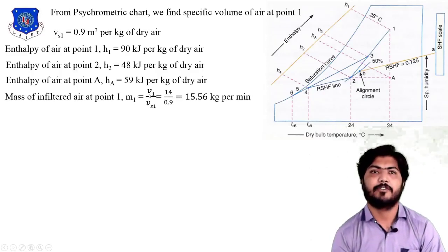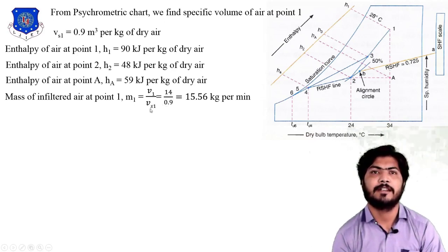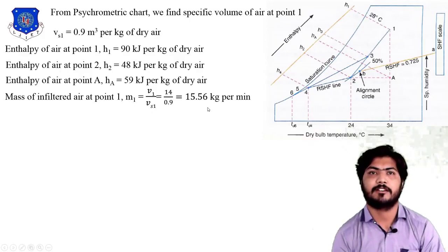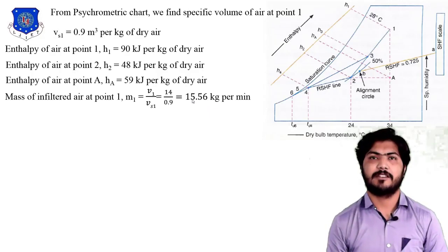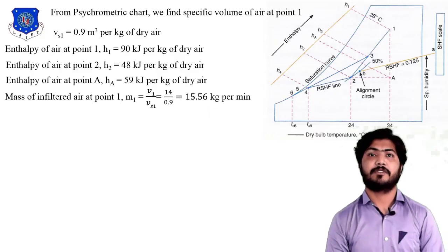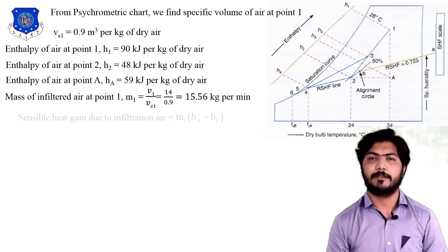Next is the mass of infiltrated air. To calculate the mass of infiltrated air: total volume is 14 cubic meters per minute divided by specific volume of 0.9 cubic meters per kg at point 1, which gives the mass of infiltrated air entering the room as 15.56 kg per minute.